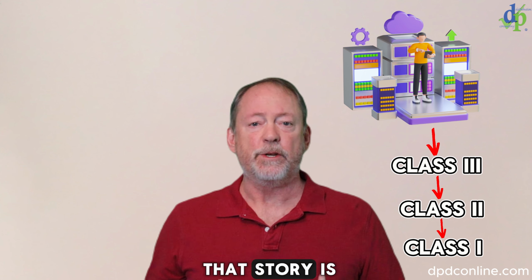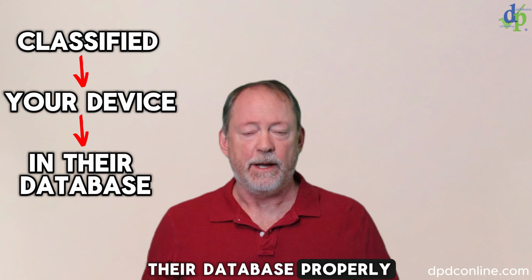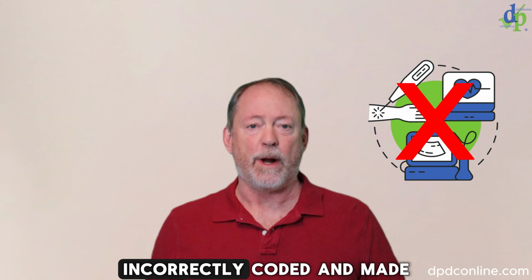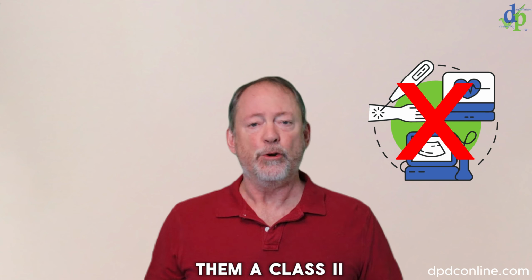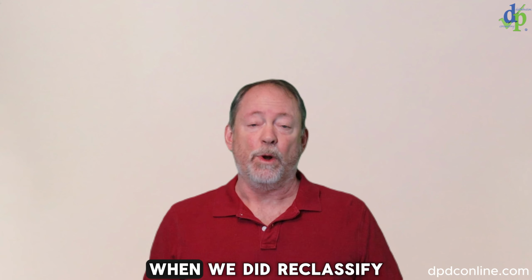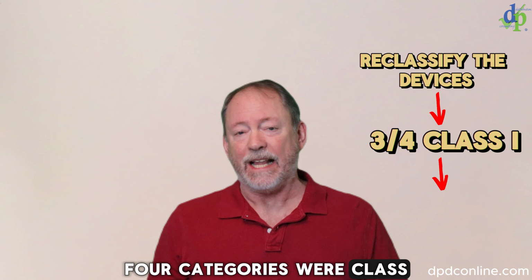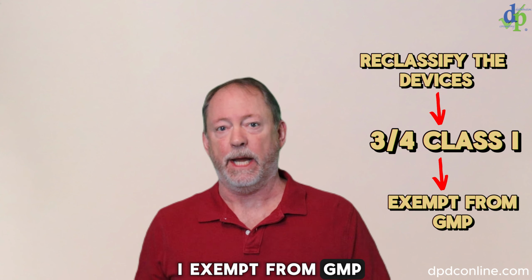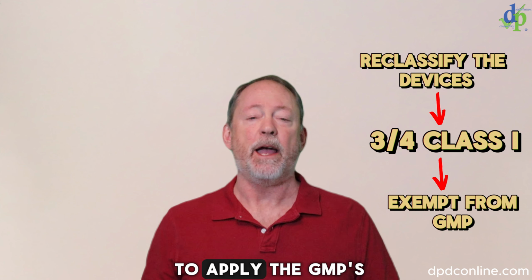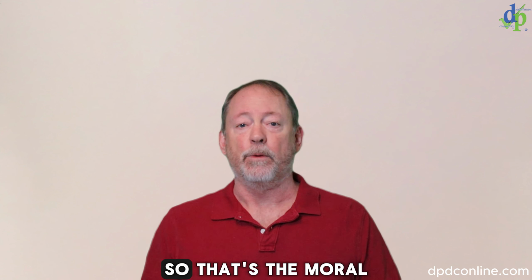Okay, so the moral to that story is you got to make sure that you have classified your device in their database properly. When we went to this facility, it turned out that they had several of their devices incorrectly coded and made them a class 2 as opposed to a class 1. And even further than that, when we did reclassify them correctly, 3 out of the 4 categories were class 1 exempt from GMP. What that means is they didn't even have to apply the GMPs or the QSRs to their devices for the most part. And that's where they actually had the findings. So that's the moral of that story.